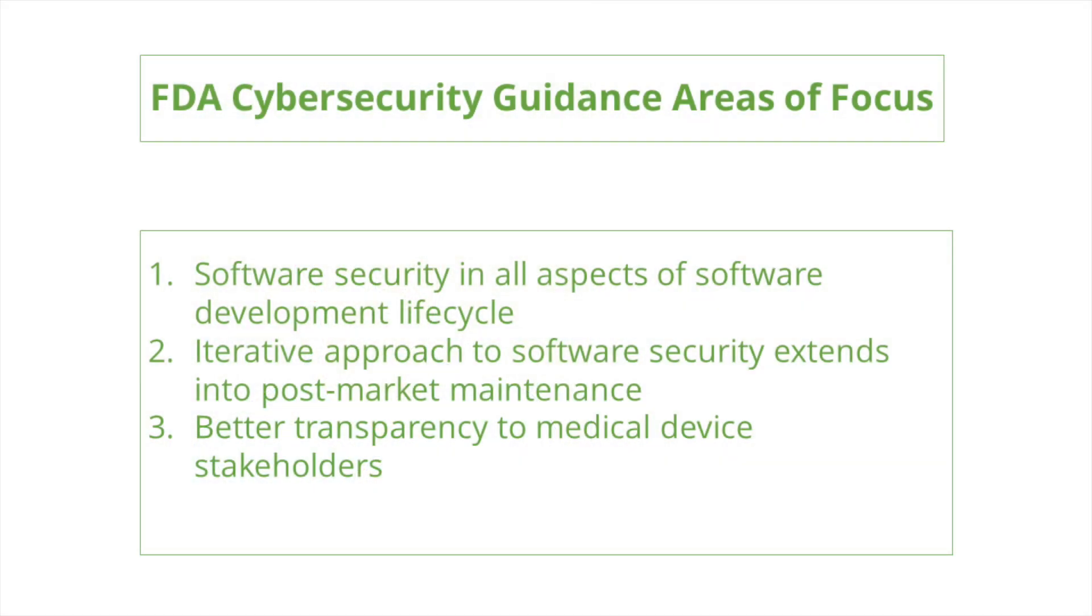The new FDA guidance on cybersecurity has three main focuses: to ensure that software security is included in all aspects of the software development lifecycle, ensure that an iterative approach to software security extends into the post-market maintenance, and provide better transparency to medical device stakeholders such as hospitals and service providers.